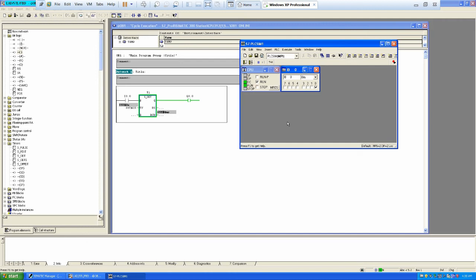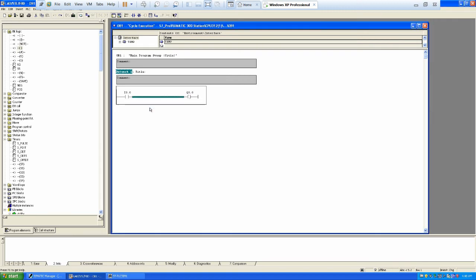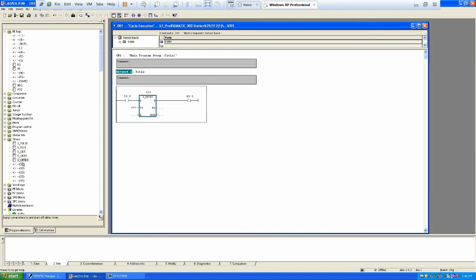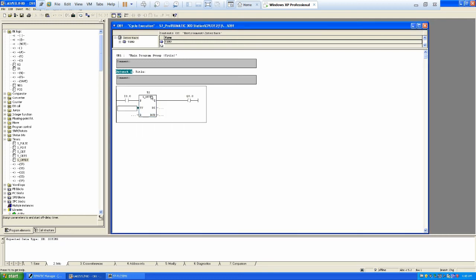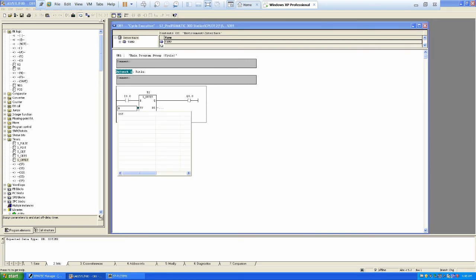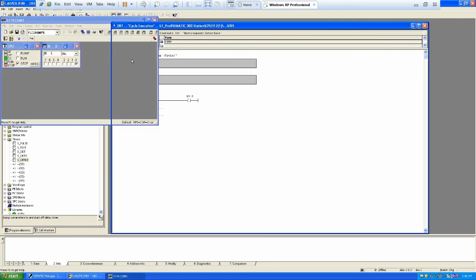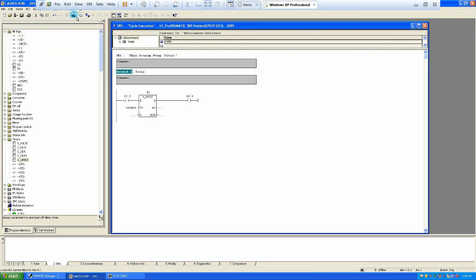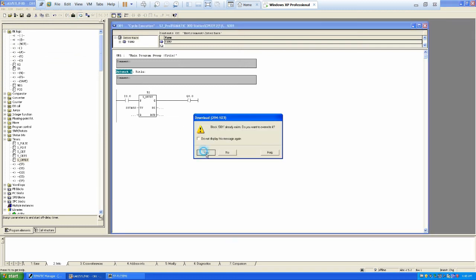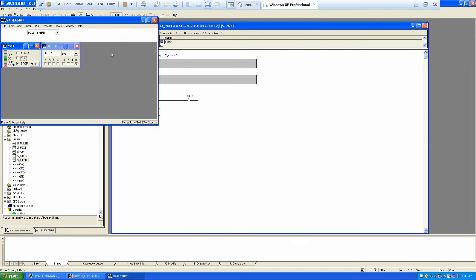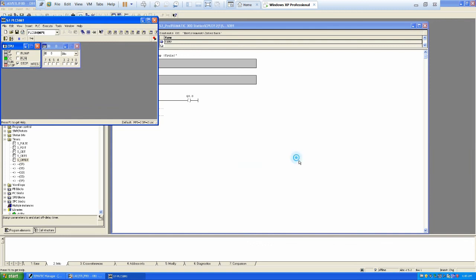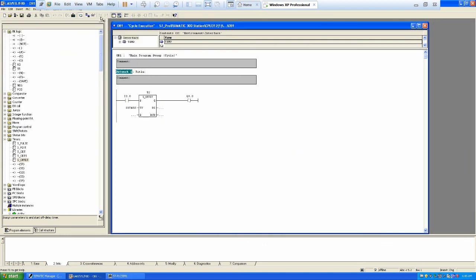So then there is another type of the timer, that's off-delay timer. We covered on-delay timer, and now we will cover off-delay timer. So I just take an off-delay timer from here and I just bring it in here. So what we will do here, we will just name it T, for example 2. And S5T number sign, how much time you need, for example 5 seconds. So 5 seconds, and then that's it. Let's now try to download and simulate the same stuff. I'm going to download it. So it's downloaded.